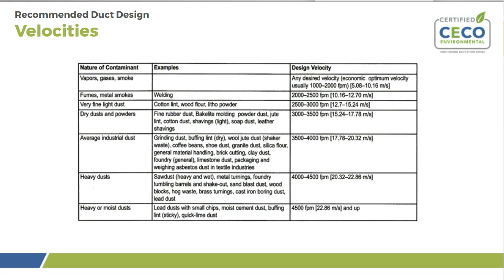If it's a heavy or moist dust, like lead, cement, anything that has the ability to cling to the inside of the duct, you want to go up to 4,500. And we've even done, on a rubber plant where the stuff stuck to the inside of the duct on a regular basis and posed a potential fire and explosion, we've gone as high as 5,000.